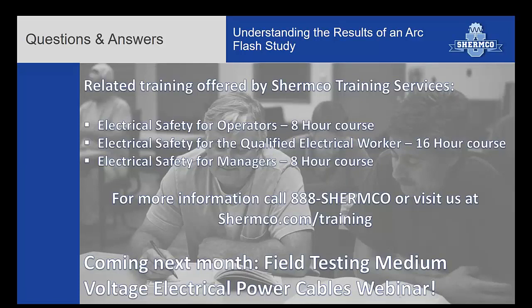I think we had a couple other ones in here, Mark. Let's see. Let me get this question right here. I noticed when looking at our arc flash study that most of the high incident energy areas are in the 480 volt gear. The medium voltage system had very few areas with incident energy over 40 cal per centimeter squared. Is that typical? Yeah, I think that's pretty typical.